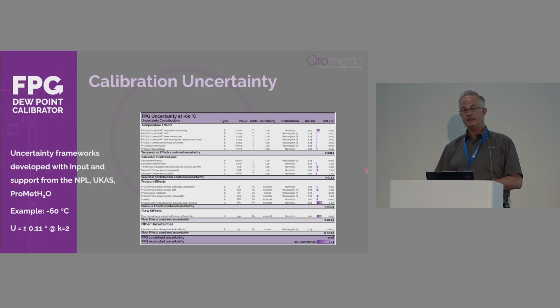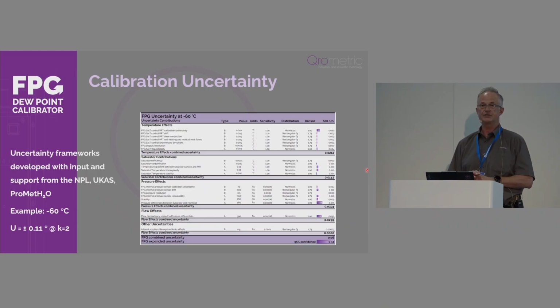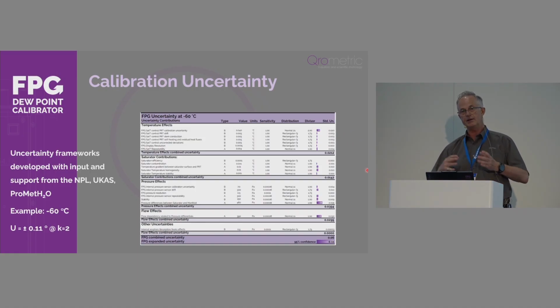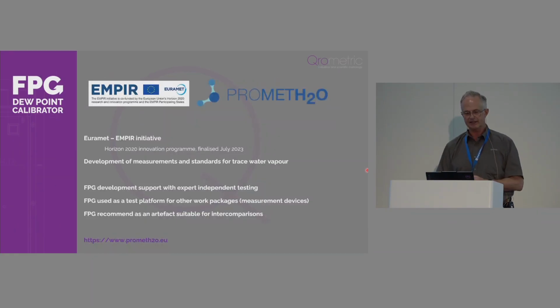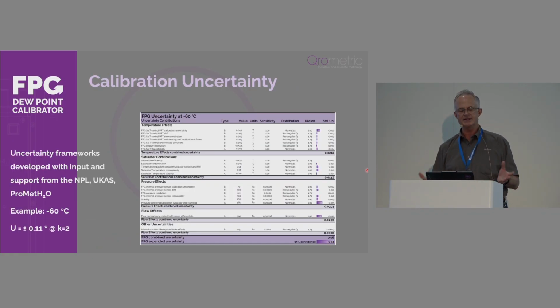In terms of uncertainty, we are specializing in calibration systems. That's our primary focus. So we always have to define the performance of the system in terms of an uncertainty with a 95% confidence at k=2. With input from UKAS, our accreditation body, the ProMetH2O project, which I'll explain second, and the NPL, we've been able to form a calibration picture, if you like, to give an expanded uncertainty, typically at -60 of 0.11 dew point. Sensors have a specification usually at that value of about ±2, so we have a very good test uncertainty ratio for the performance of the system.